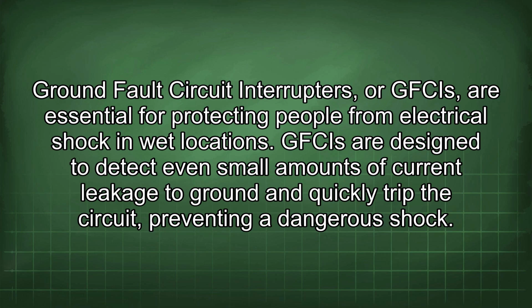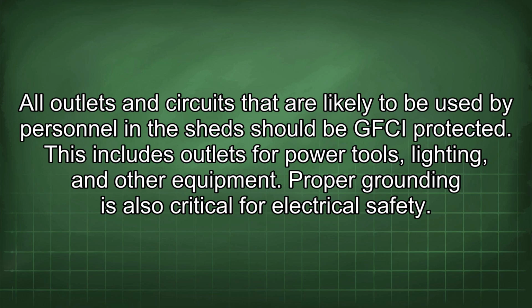Ground fault circuit interrupters, or GFCIs, are essential for protecting people from electrical shock in wet locations. GFCIs are designed to detect even small amounts of current leakage to ground and quickly trip the circuit, preventing a dangerous shock. All outlets and circuits that are likely to be used by personnel in the shed should be GFCI protected. This includes outlets for power tools, lighting, and other equipment.